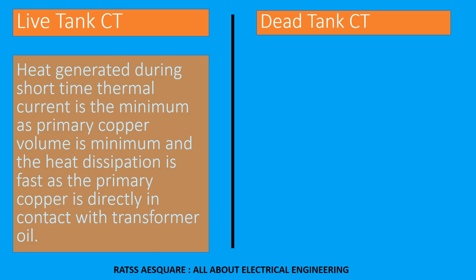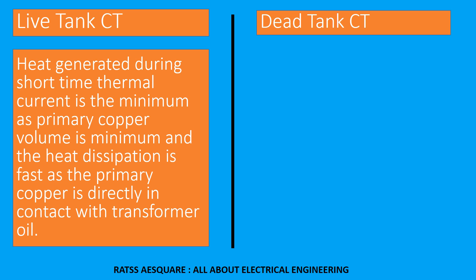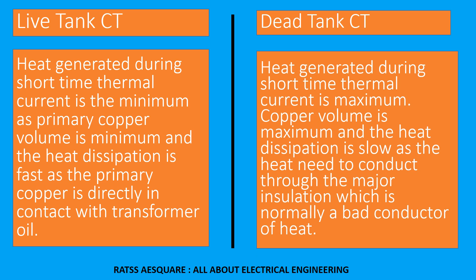In live tank CT, heat generated during short-time thermal current is minimal, as primary copper volume is minimum and heat dissipation is fast since the primary copper is directly in contact with transformer oil. In dead tank CT, heat generated during short-time thermal current is maximum — copper volume is maximum and heat dissipation is slow, as the heat needs to conduct through the major insulation, which is normally a bad conductor of heat.